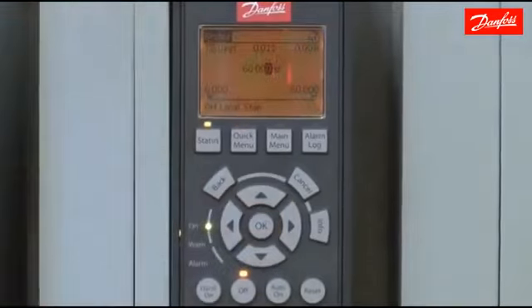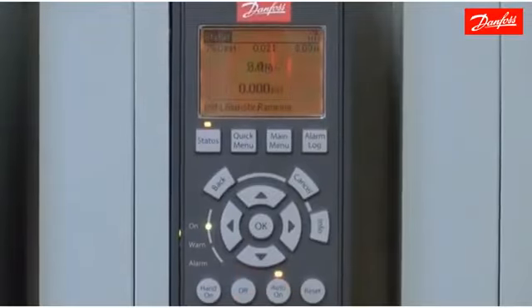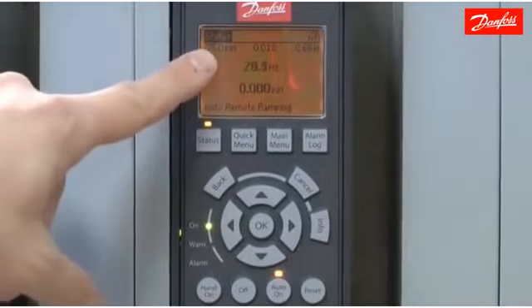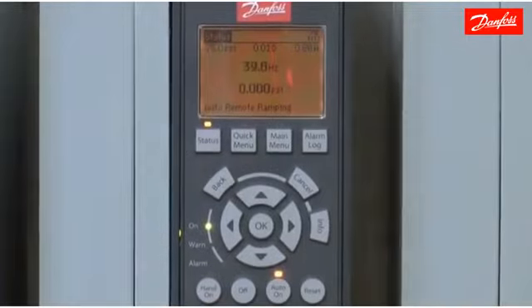And essentially I'm finished with the setup. Closed loop, constant pressure, put the drive in auto mode, and it's ready to go to maintain a set point of 75 psi based on feedback.